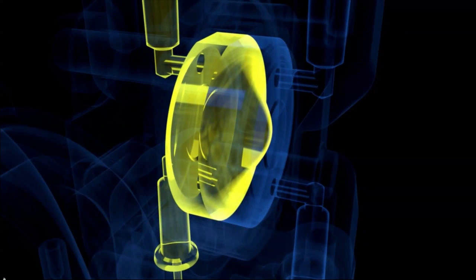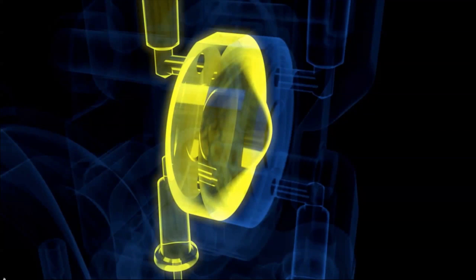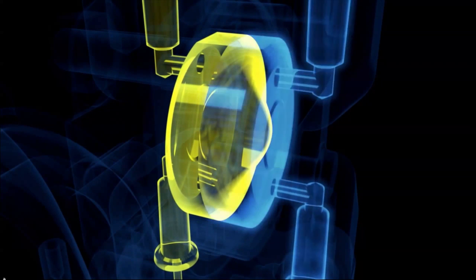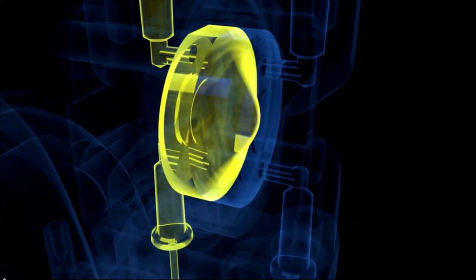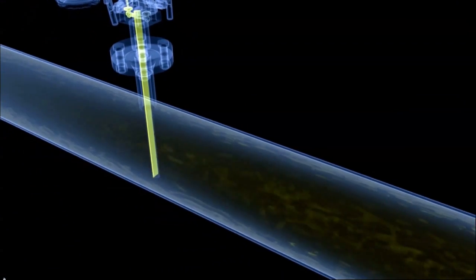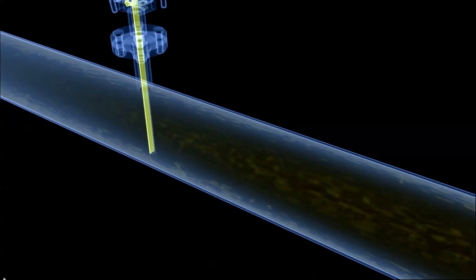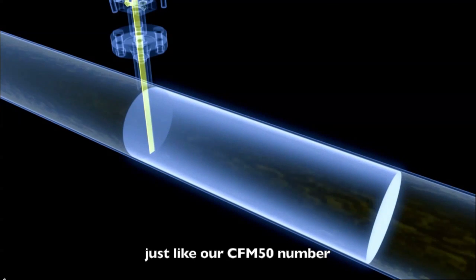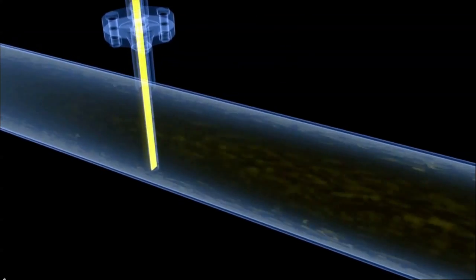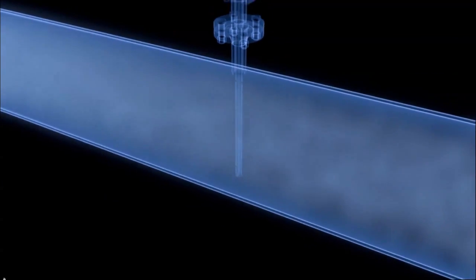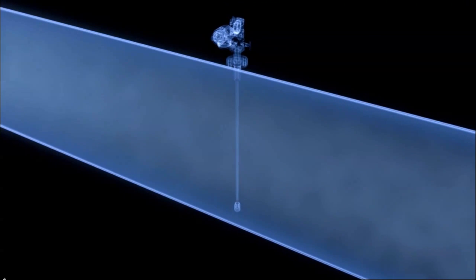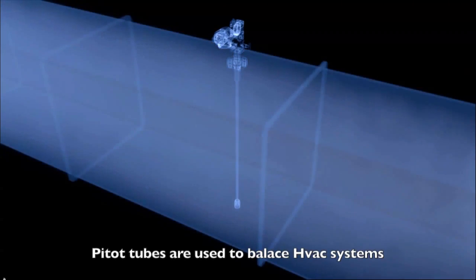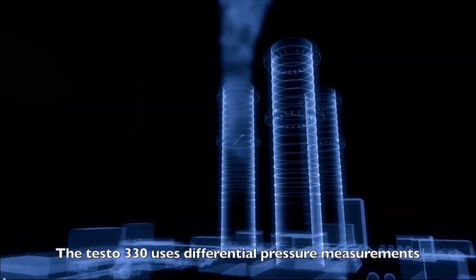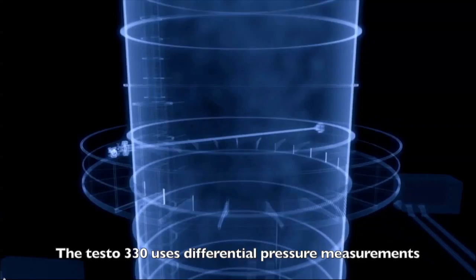As a result, different values are detected in the pressure chambers of the sensor. Higher pressure against the flow and constant pressure on the rear of the pitot tube. This pressure difference is a direct measure for the flow velocity and thus the mass and volume flow in the pipe. The higher the flow velocity, and therefore the dynamic pressure, the greater the differential pressure measured. A unique feature is that pitot tubes can register flows in extremely large pipelines. This advantage applies not only to square ventilation ducts, but also to the measurement of flue gas or exhaust emissions in large chimneys of up to 12 meters in diameter.